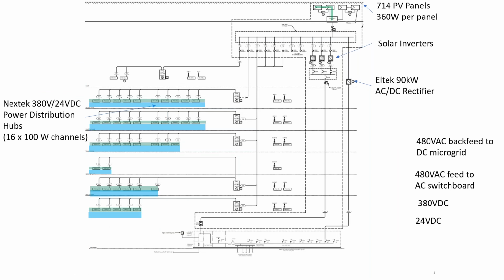So here we are showing the DC distribution for the AGU that utilizes the existing electrical 208/120 volt infrastructure that was part of the 1992 renovation and the new 380 volt DC microgrid powered by the photovoltaic system. As I mentioned before, the overall capacity of the PV system is approximately 258 kVA based on 714 360-watt SunPower modules. The design intent for the 380 volt DC microgrid is to directly utilize the generated DC power for the majority of the LED lights and workstations, while any excess power is backfed to the utility.